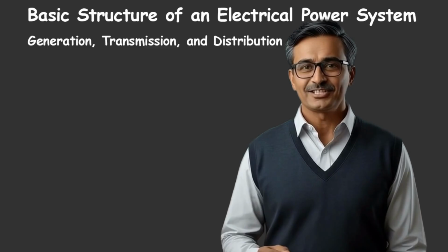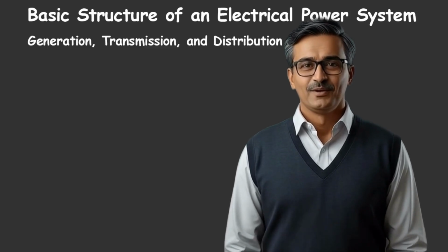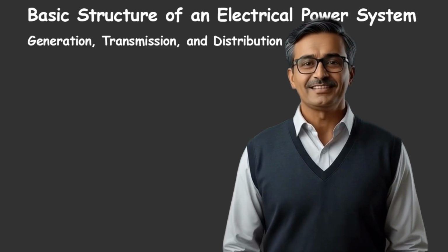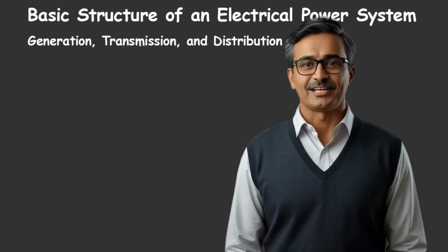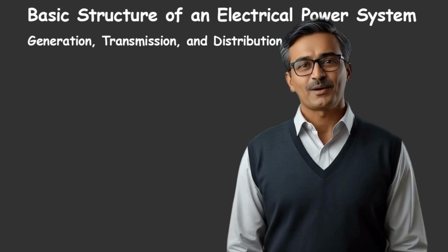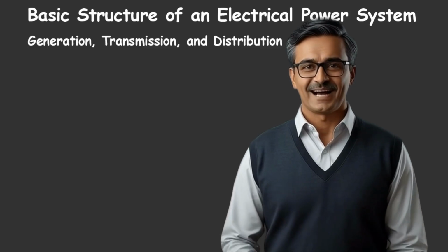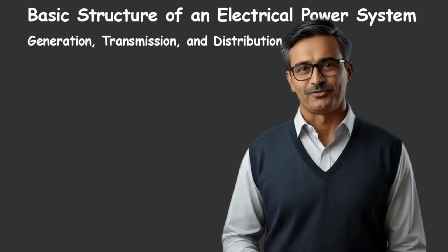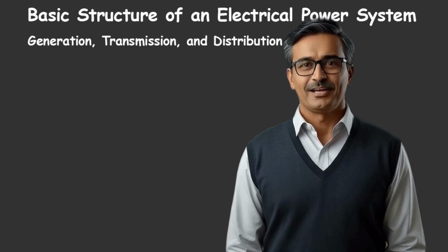So after generation, the power system steps up this power to a high voltage level. This is because high voltage transmission reduces the current for the same amount of power. Reduced current reduces I²R losses, improves voltage regulation, and also reduces the required conductor cross-section and weight.